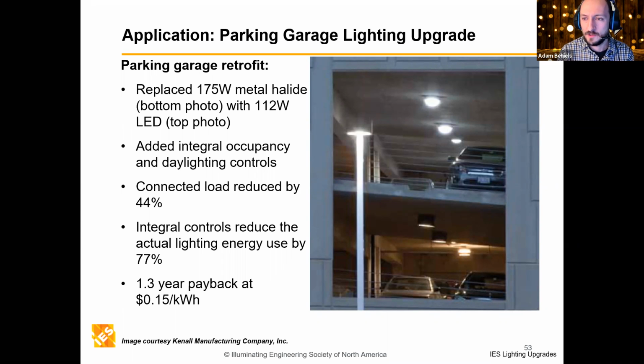One thing to consider when doing parking garages: try to keep the existing layout to limit new wiring and conduit needed for your new fixtures. You'll weigh this against the fact that if you did add that wiring, you could use lower cost luminaires instead.